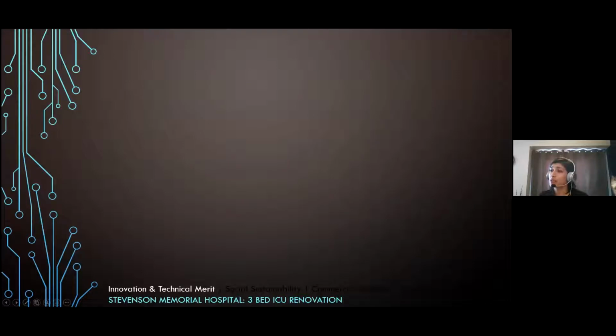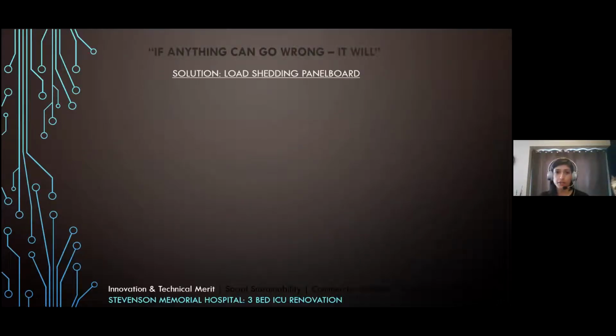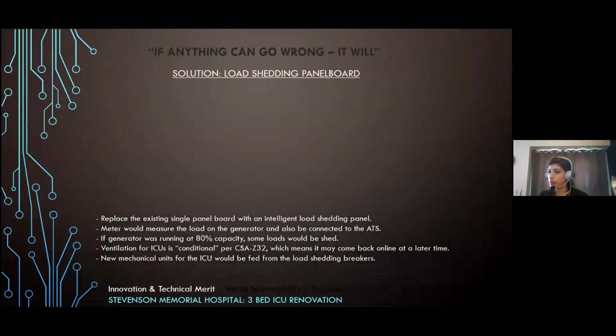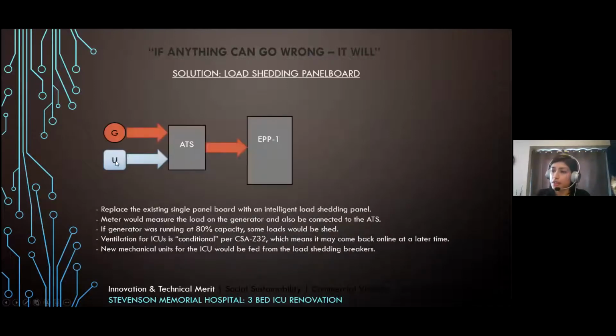So we had to come up with a solution. Our solution was a load shedding panel board. So I'm going to show you a very, very simplified single line diagram of our distribution. On the left, this U represents utility power, and the G represents generator power, and the ATS is an automatic transfer switch.